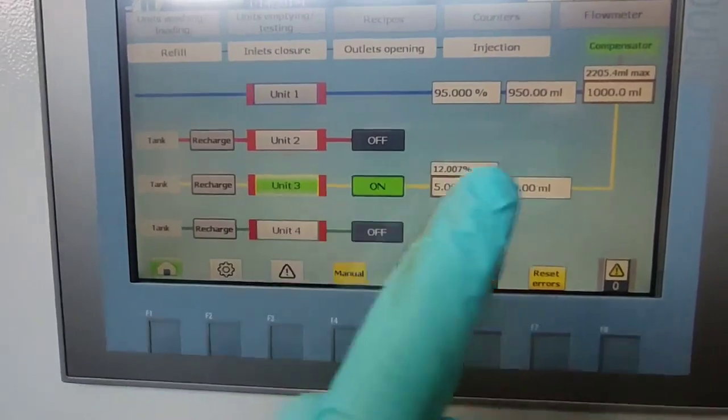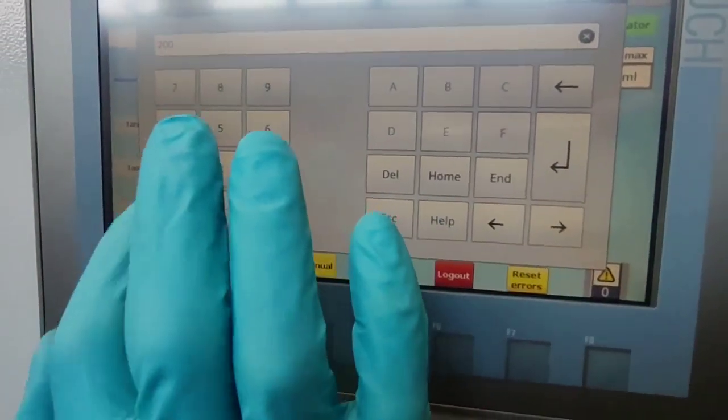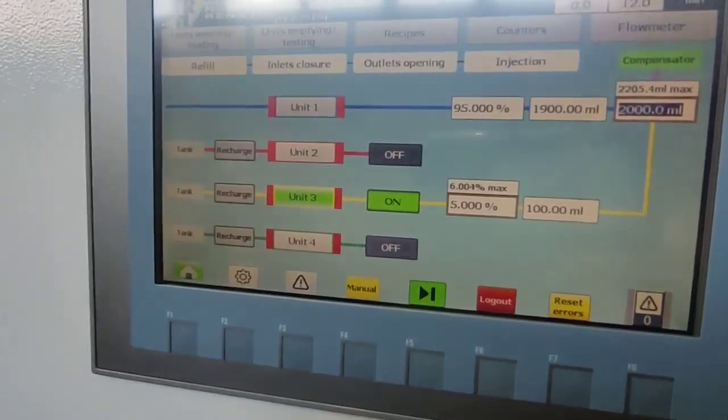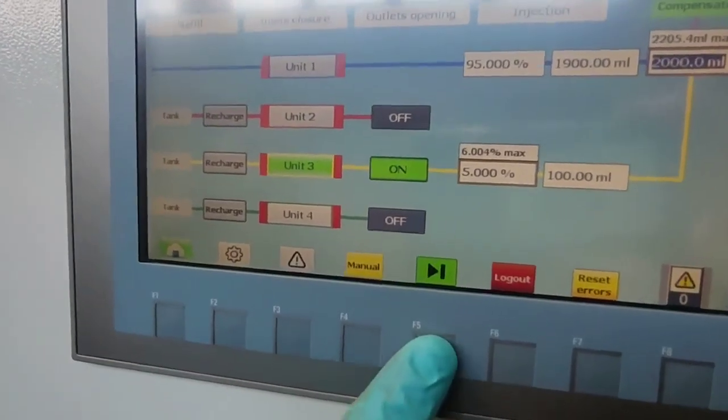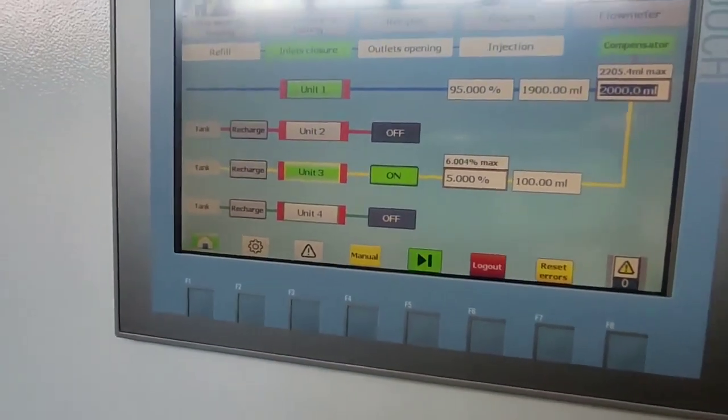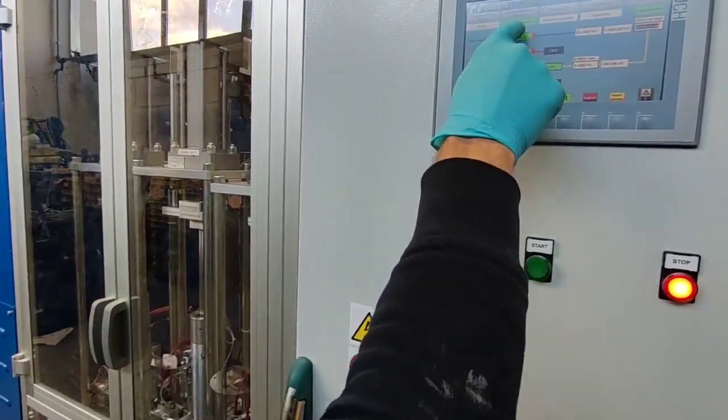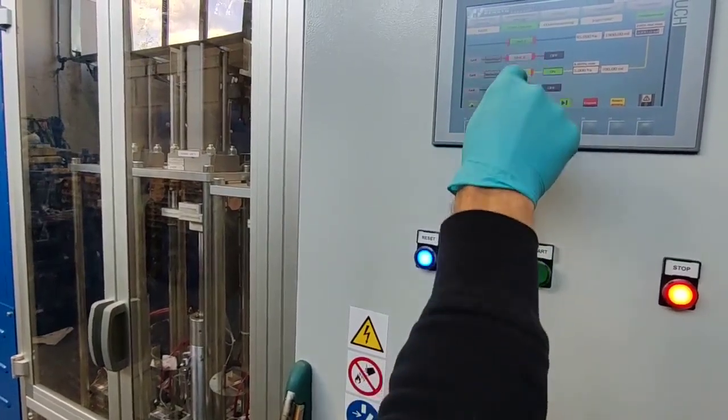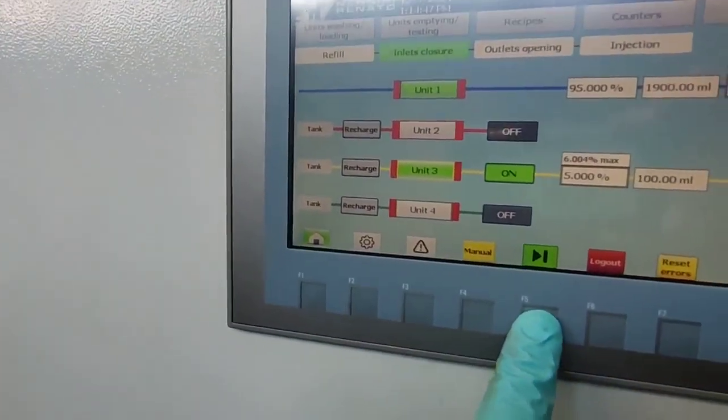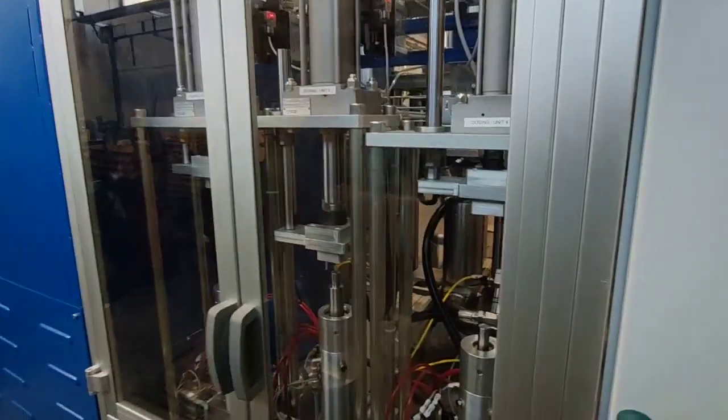In this moment we are going to do one liter, but we can also set two liters if you want. We are doing five percent of dosing unit three additive. I push this button in order to charge the dosing units. Now the dosing units are ready. You can see that both are green, so we can push again this button to start the next part of the procedure and the dosing units are dosing out the product.